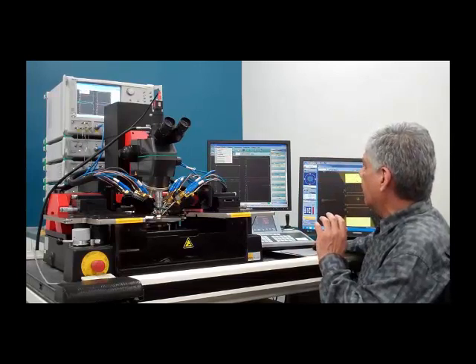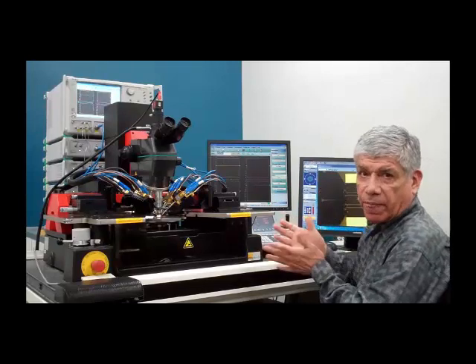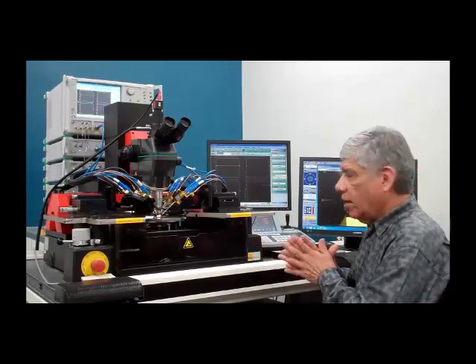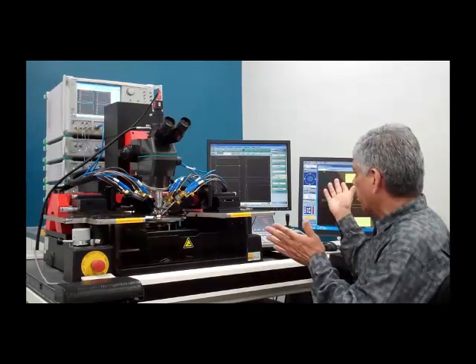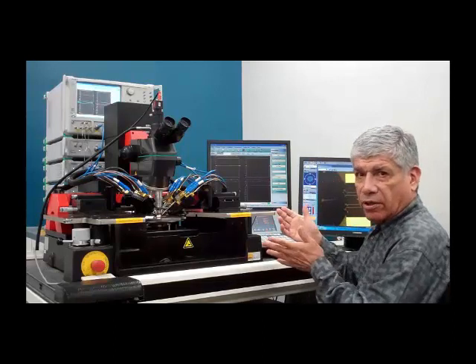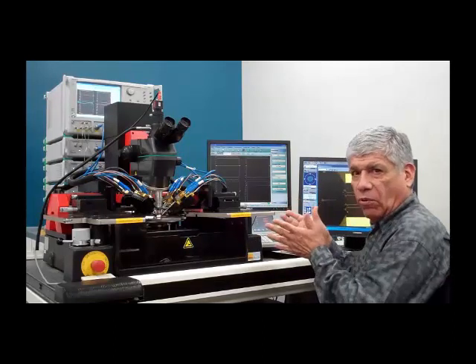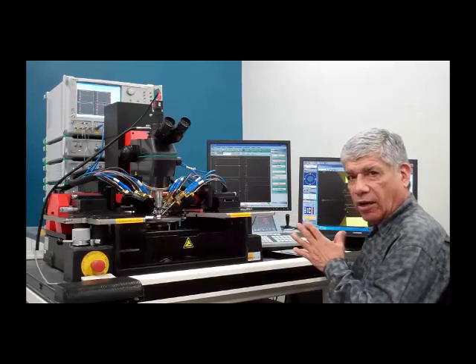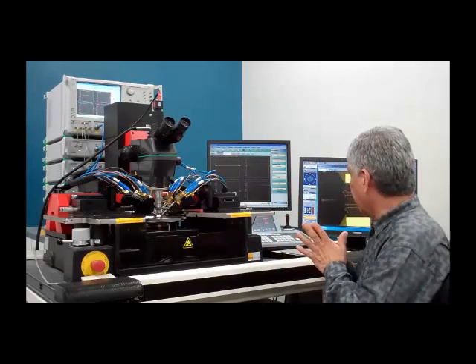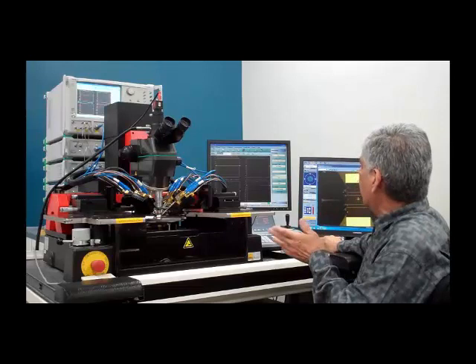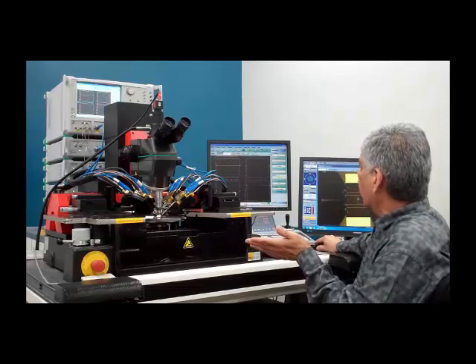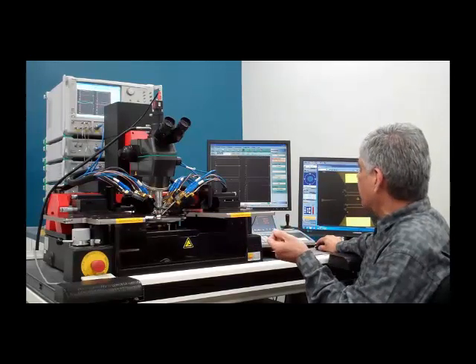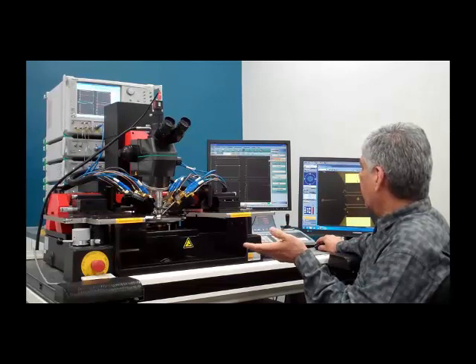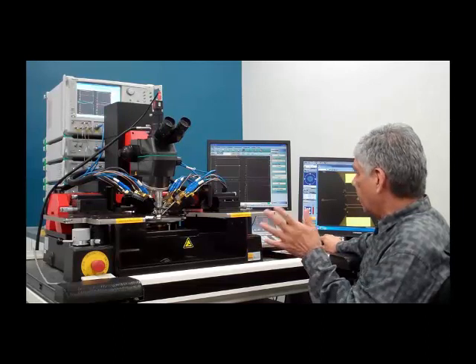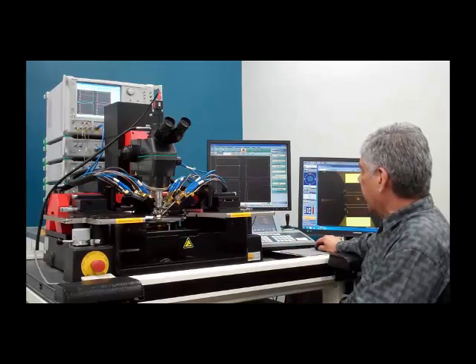Other areas of interest would be, for instance, averaging. We set our IF bandwidth. In this case, I just have it at 1 kilohertz, but you could set it to 100 hertz or whatever dynamic range requirements are needed. So once we have our frequency, power and averaging set up, then we're ready to start setting it up for the display that we want to look at.